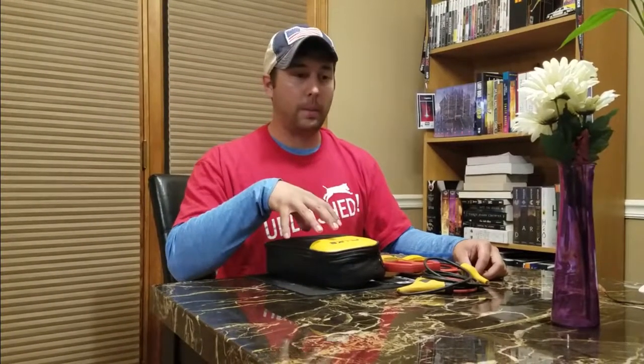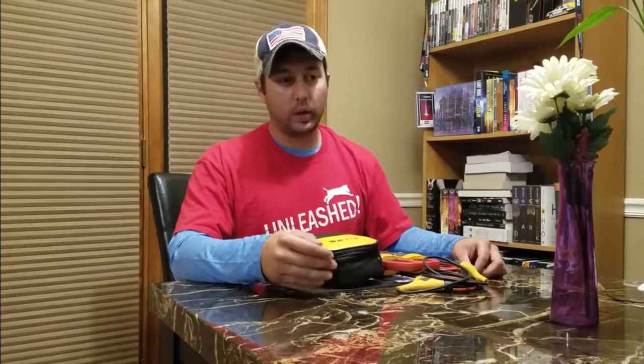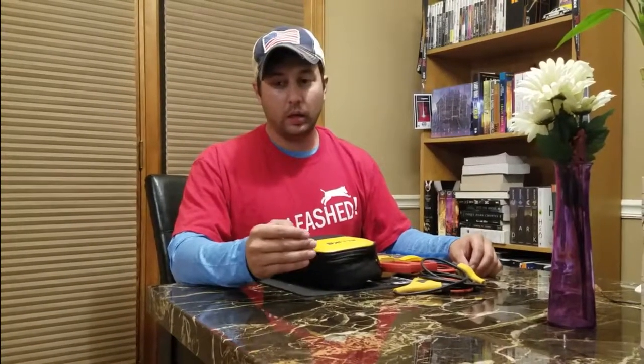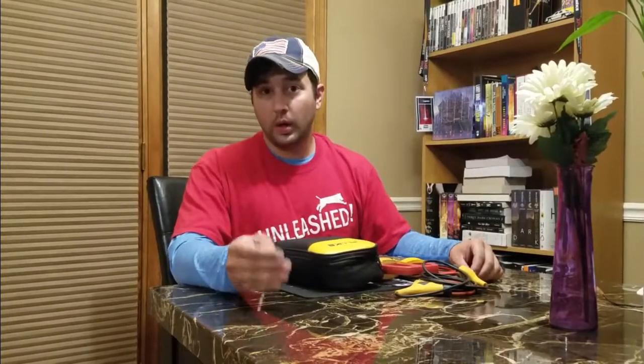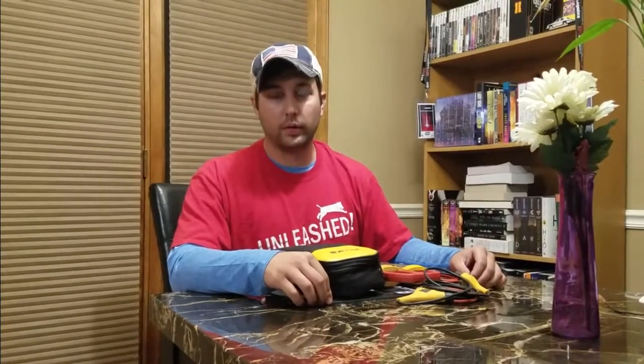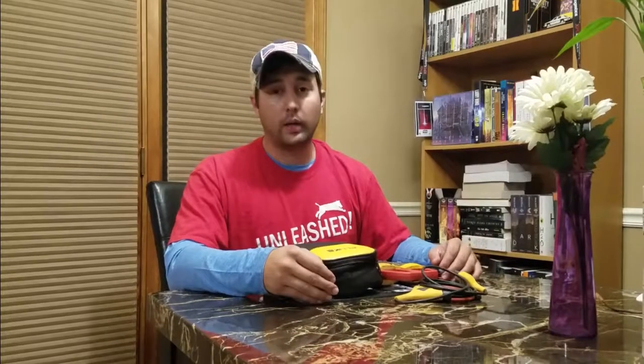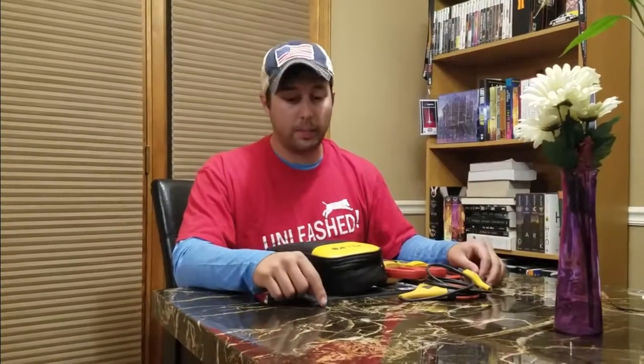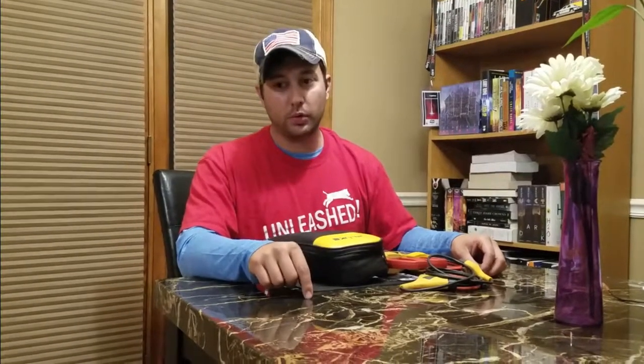The situation we had going on was the neutral was broken. The maintenance guy came out and said there's nothing wrong, you have 120 volts power in your camper. I said, no, you have a broken neutral, an open neutral somewhere, because the power needs to go back to neutral.